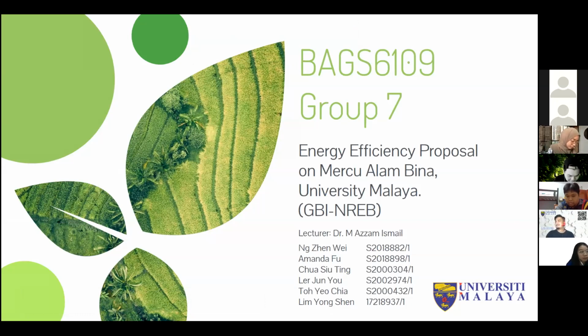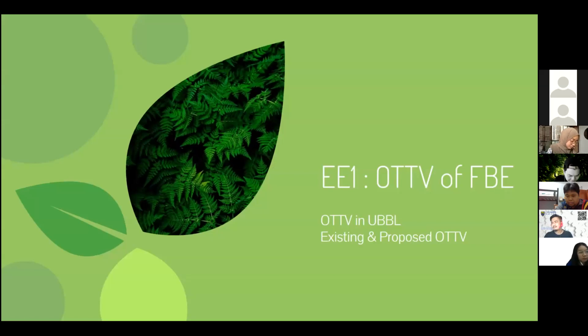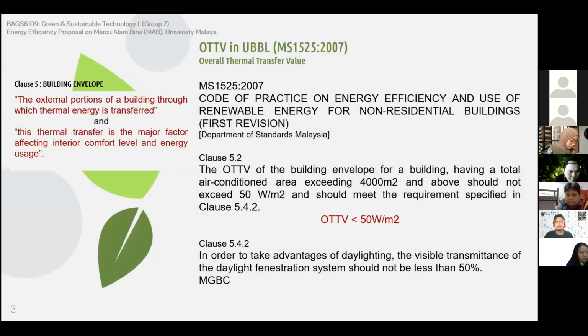I will start with the minimum energy efficiency performance of OTTV of FBE. As a brief background, OTTV is under Malaysia standards, clause number 5, building envelopes, defined as the external portions of buildings through which thermal energy is transferred. This thermal transfer is the major factor affecting interior comfort level and energy usage. According to clause 5.2, the OTTV needs to be less than 50 watt per meter square.